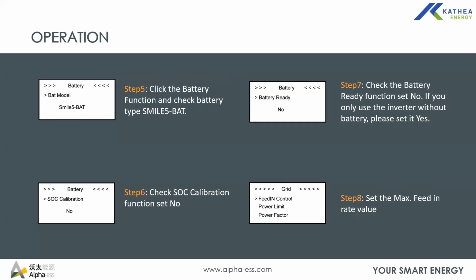If you intend to use the inverter as a grid tie inverter, that's where you access the battery ready setting. As I've said, if battery ready is set to no, it means the inverter needs to be connected with batteries. However, if the inverter is to be used as a grid tie without batteries, you need to set battery ready to yes, to give it a virtual battery scenario.